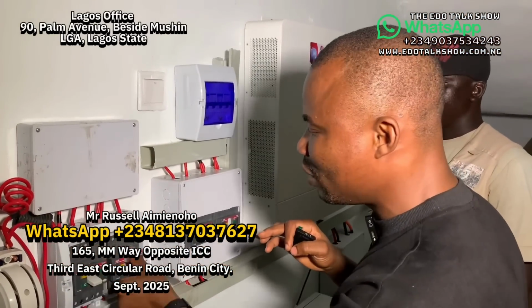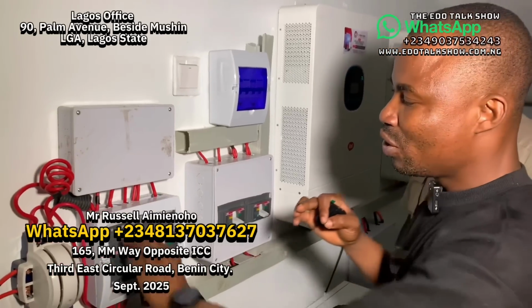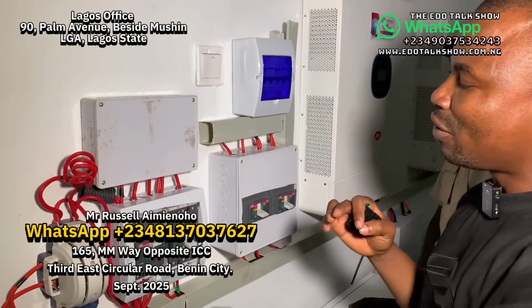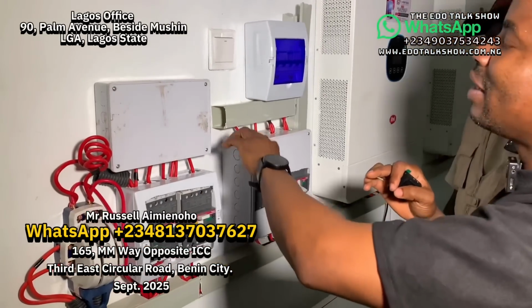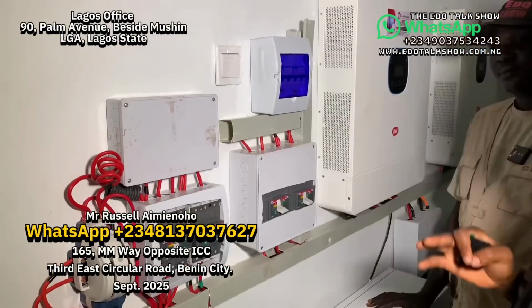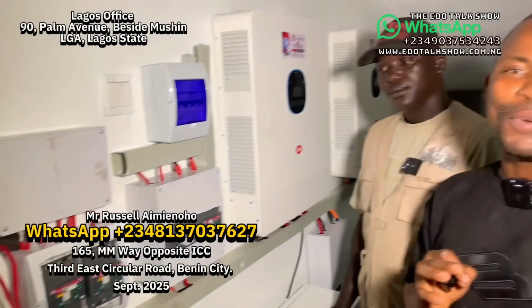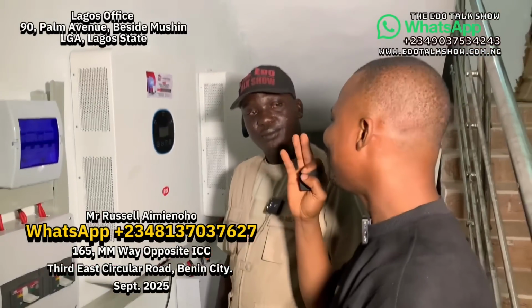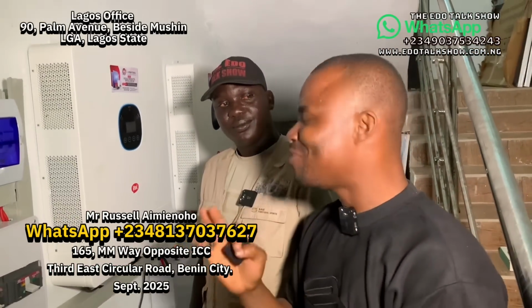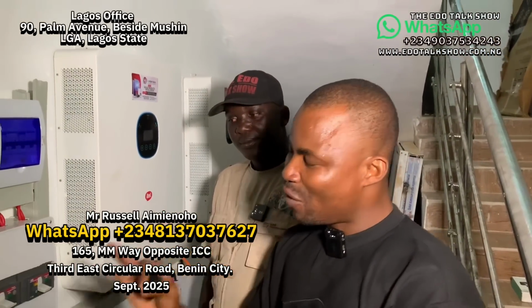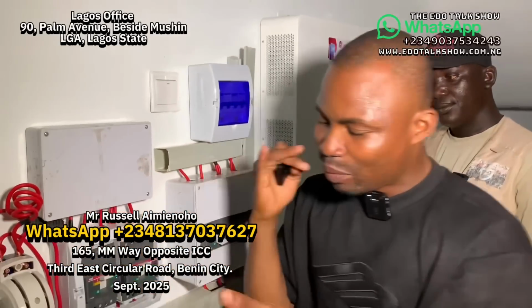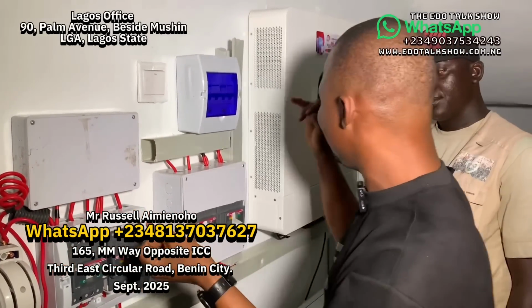So if we switch off these two breakers, the light goes off. If we switch on one breaker, the light comes on. If I switch on the second one, it supplies too. The two lights sync together, no spark, no burning. Why? Because of a special package, as I told you, we're able to program the inverter. Here at the bus bar, we connect positive to positive for this inverter.